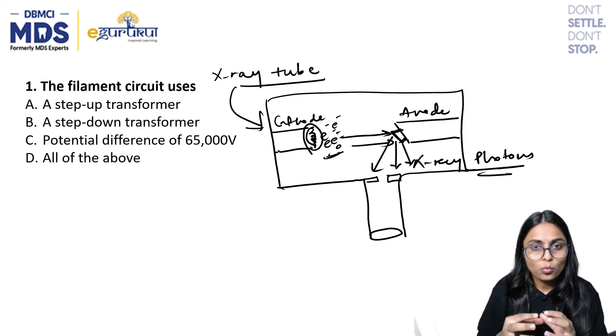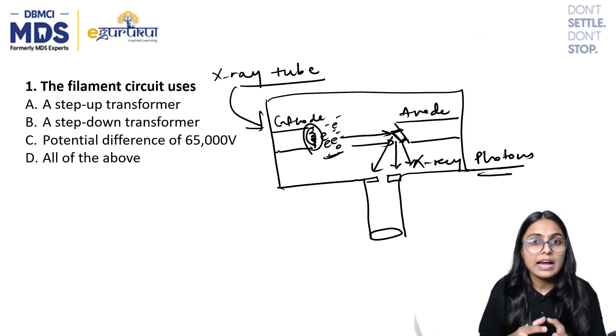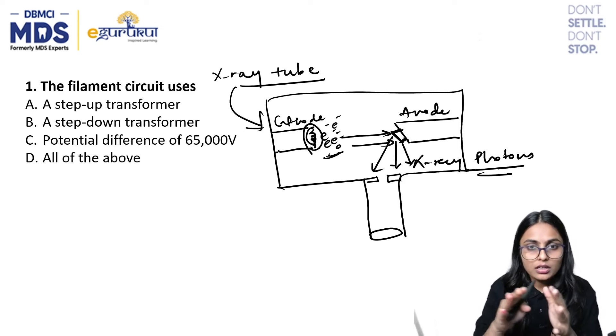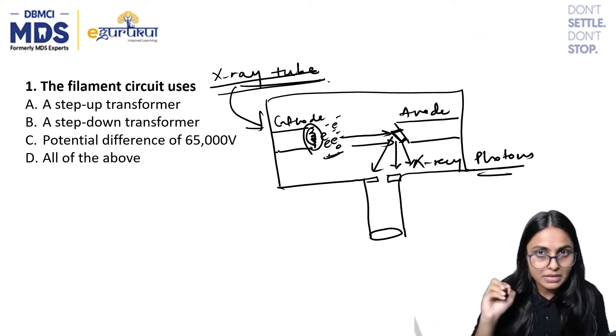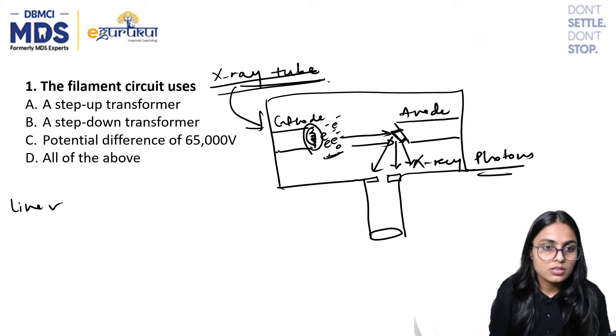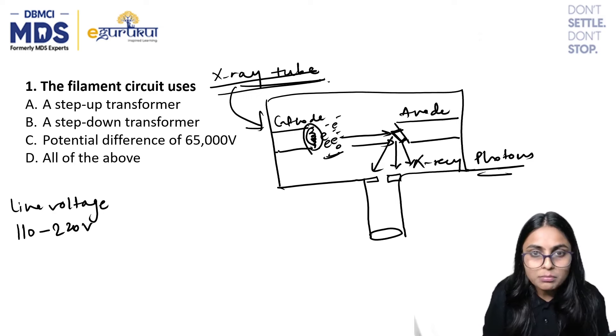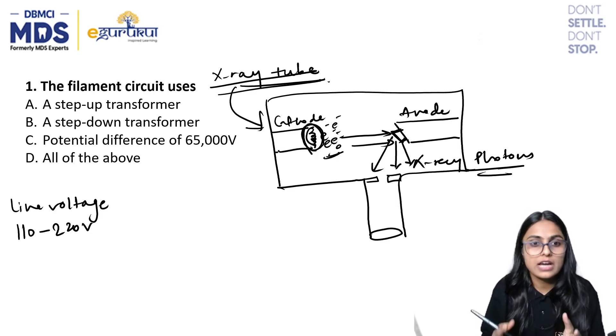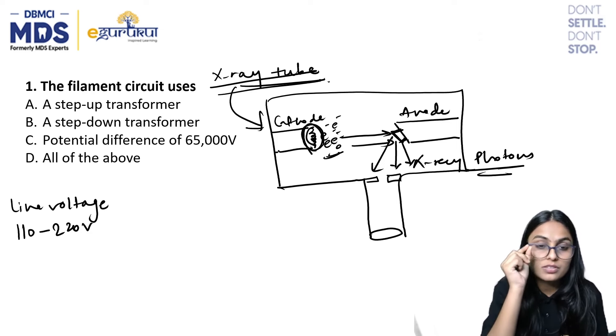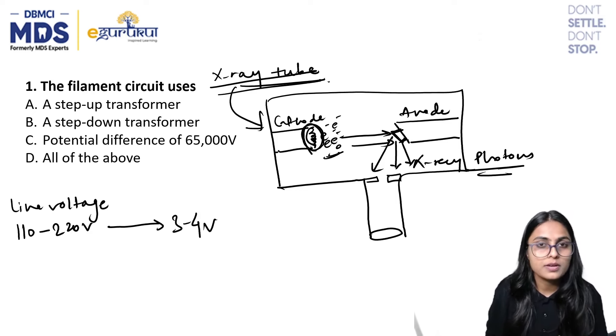What exactly happens with the transformers inside the X-ray machine? When you studied the structure of the X-ray tube, we had a step-up transformer, step-down transformer, and auto transformer. When you switch on the X-ray machine, the line voltage is normally 110 to 220 volts. To heat up the tungsten filament, we do not require that much voltage — we only need 3 to 4 volts to heat up just 2 mm of tungsten filament.